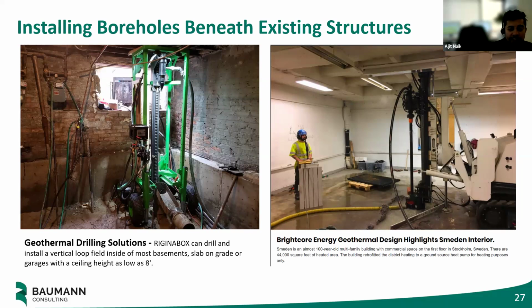We talked about installing boreholes beneath buildings. One new novel development is installing boreholes beneath existing structures. There are new technologies—I think some are Swedish—proliferating with low-height drills that can actually drill through existing slabs into the ground, with ceiling heights as low as 8 feet. So you can really do this in existing buildings. This is now slowly becoming a more viable option for commercial retrofit, even in urban settings.